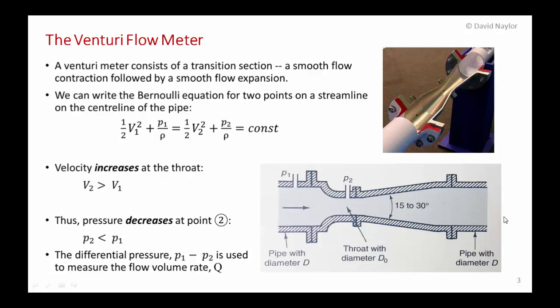A Venturi flow meter is an instrument you can insert in a pipe. It consists of a transition section where the flow is contracted and then followed by a smooth expansion. We can write Bernoulli's equation for two points on a streamline on the centerline of the pipe in the contraction zone — point one is upstream of the contraction and point two is right at the narrowest point.